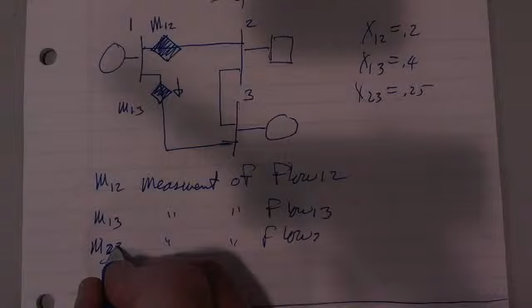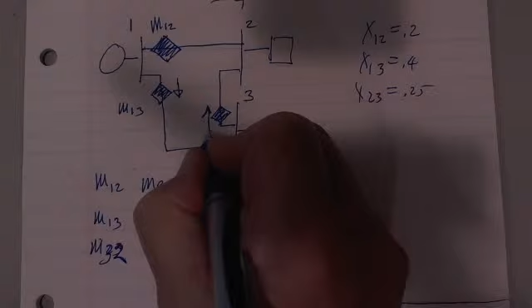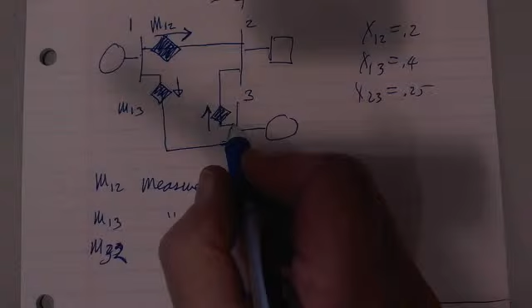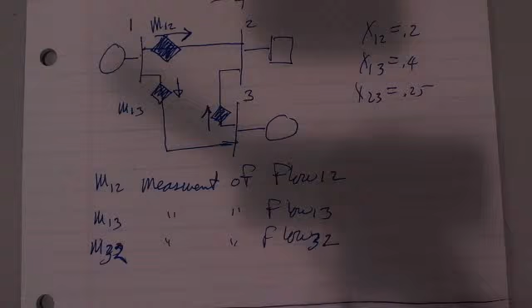Similarly M32 is a measurement of flow, actually, 3 to 2, and there's a reason for doing it that way. We always define the flow on a transmission line at the end of the bus as going away from the bus, so the equation is this minus this. So the flow here is 3 to 2.